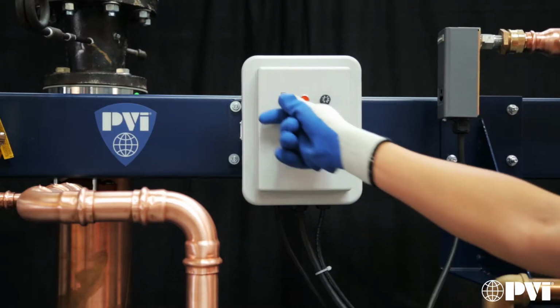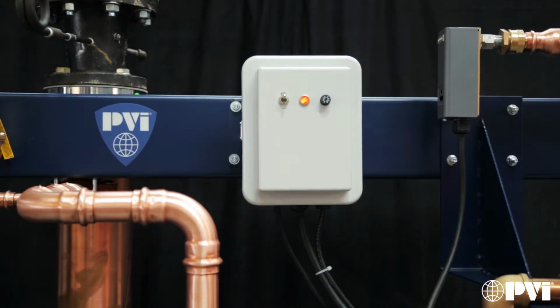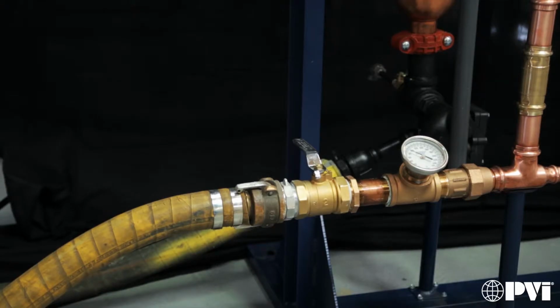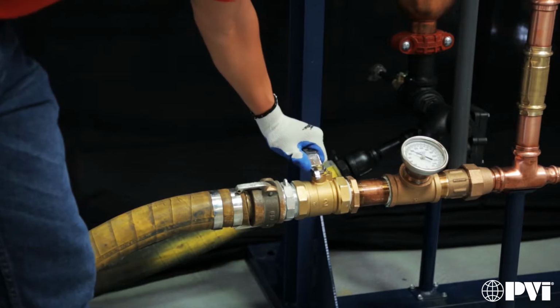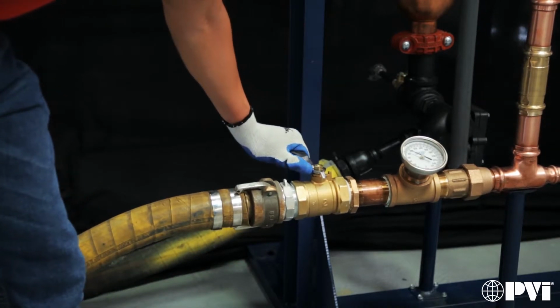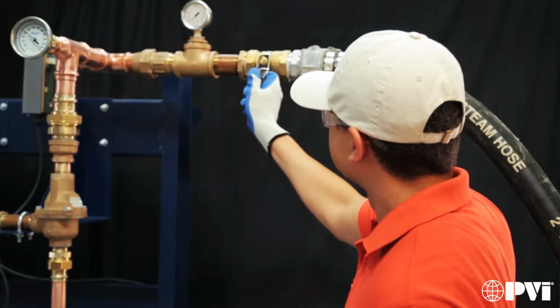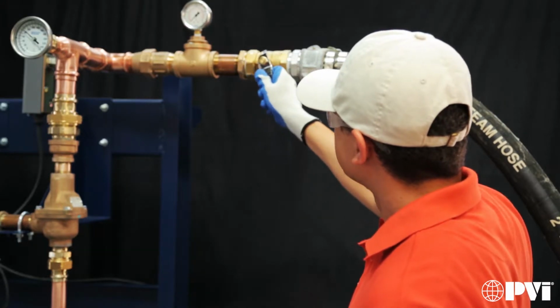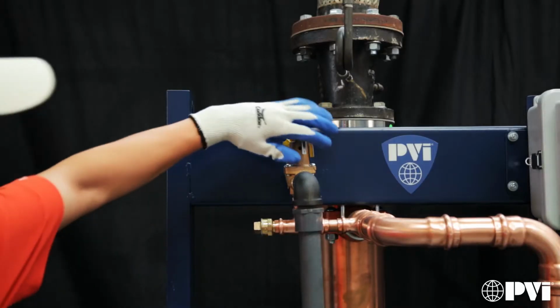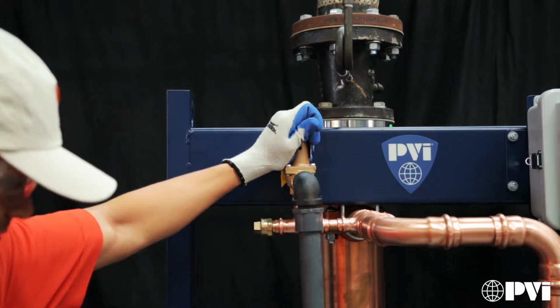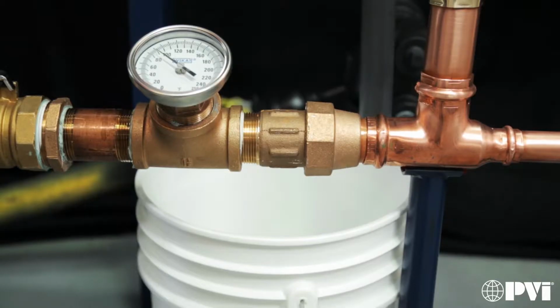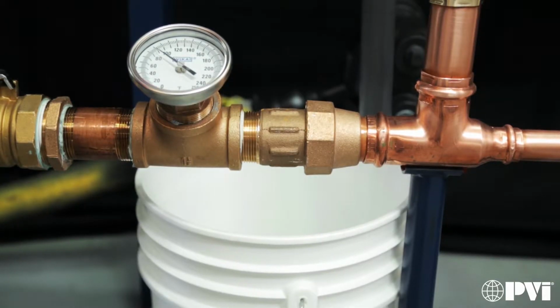Press the power switch to on. The solenoid valve should now be in an open position. Slowly open the water inlet supply valve. Check for water leaks on waterside piping. Slightly open the water outlet valve to vent air from piping. Lightly lift the pressure relief valve to assist in air removal from the heat exchanger until a steady stream of cold water exits the unit.